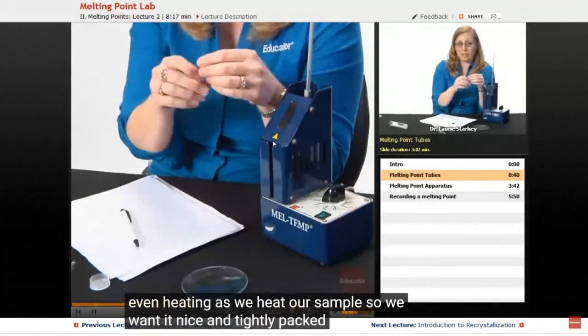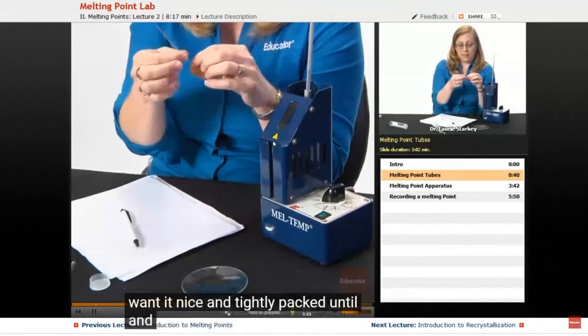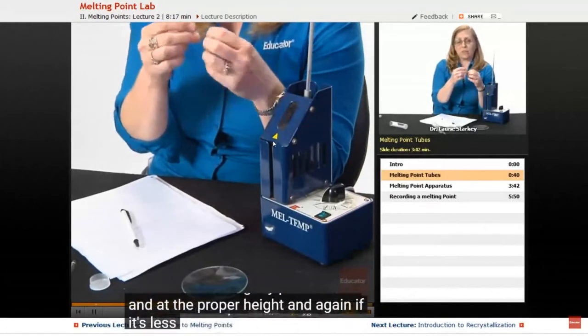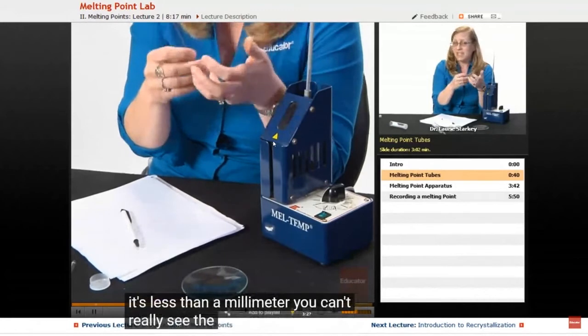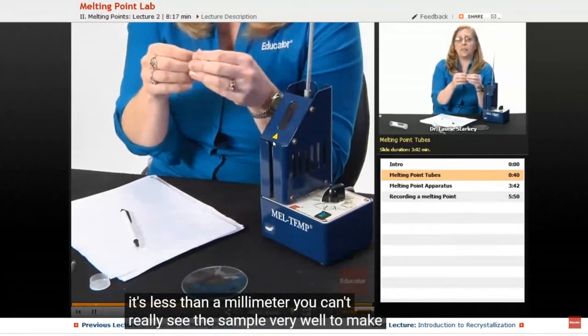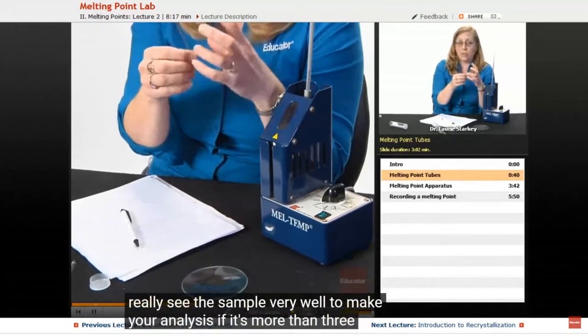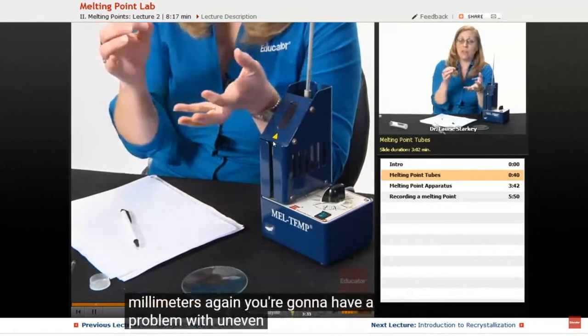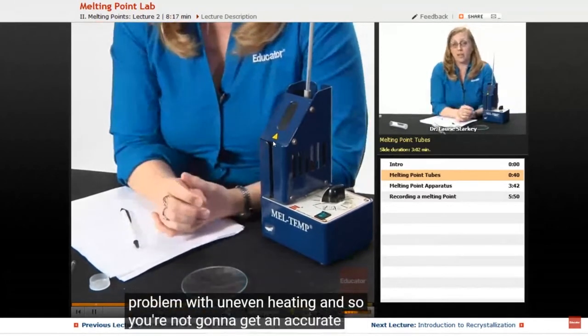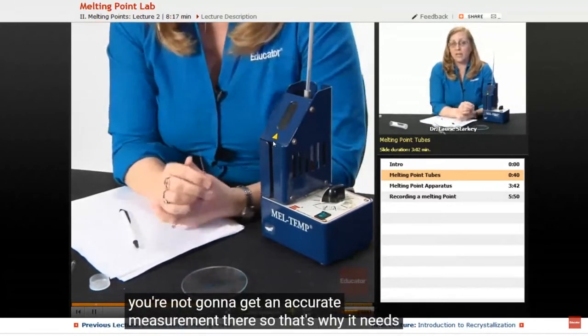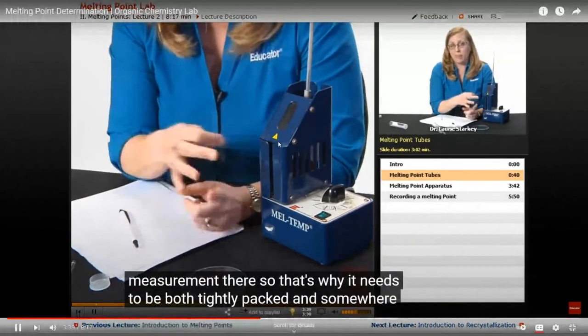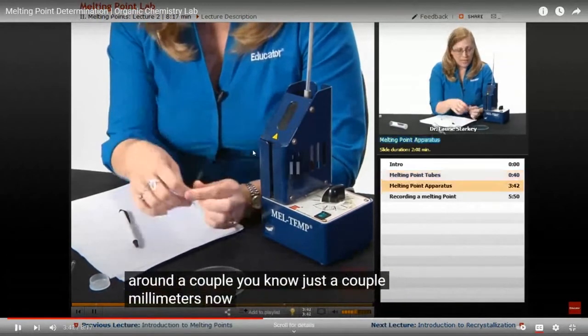So we want it nice and tightly packed, and at the proper height. Again, if it's less than a millimeter, you can't really see the sample very well to make your analysis. If it's more than 3 millimeters, you're going to have a problem with uneven heating, and so you're not going to get an accurate measurement. So that's why it needs to be both tightly packed and just a couple millimeters. So that's for the expert.